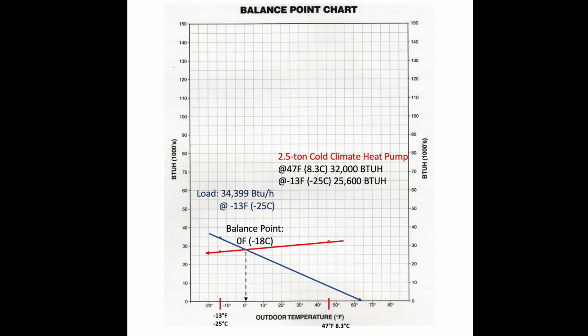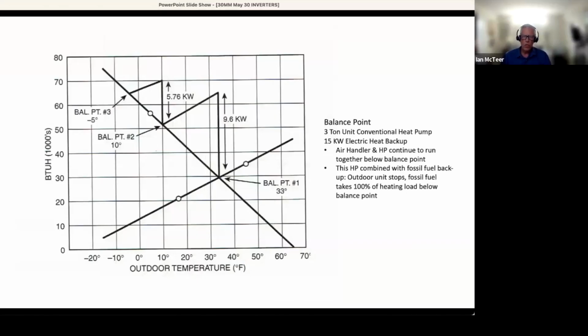You want to flip to that next slide, Doug. This is a chart we used to use in the old days where we had a staged electric furnace. So you can see that the slope on that equipment line is fairly dramatic. And in this particular case, the balance point, the point where the backup heat's going to need to come on, is at 33 degrees Fahrenheit, or what, +1 or 2, something like that.